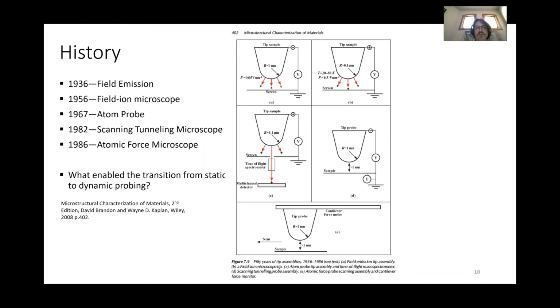And just a few years before field emission, thermionic emission was developed, I believe in the 20s. Thermionic emission is basically where you heat up a metal in a vacuum and it starts to emit electrons. Okay, so field emission is different than thermionic in that there's no heat involved, just an electric field. That's a high-level summary. We'll talk about the difference between field emission, thermionic emission and Schottky emission when we start talking about scanning electron microscopes. But anyway, it's on this slide. Figured I'd talk about it just a little bit. So 1936, field emission was developed.